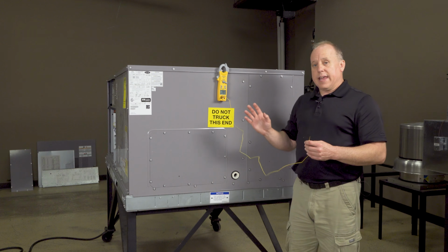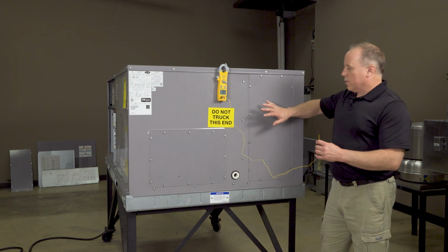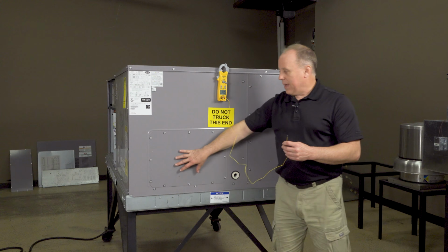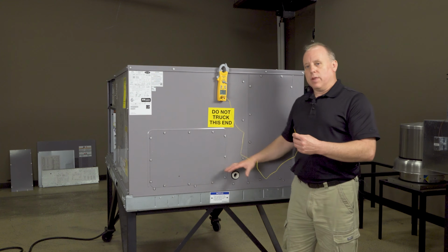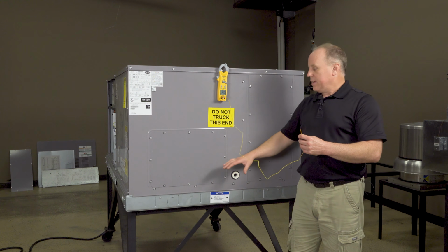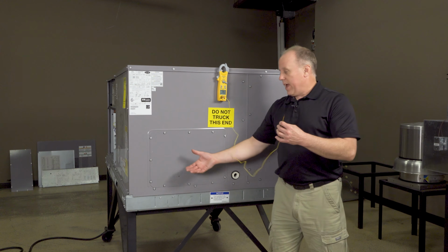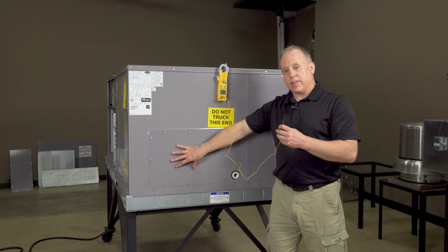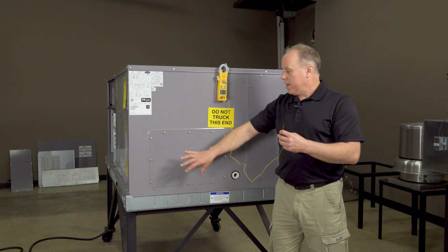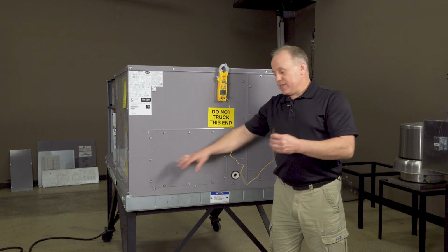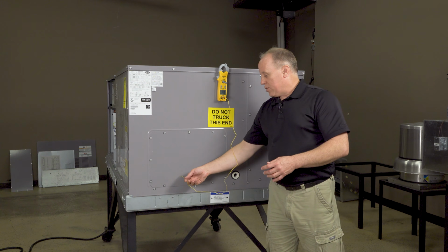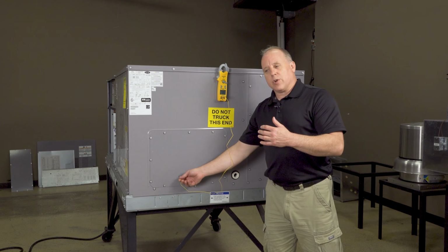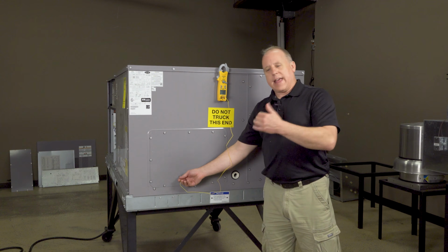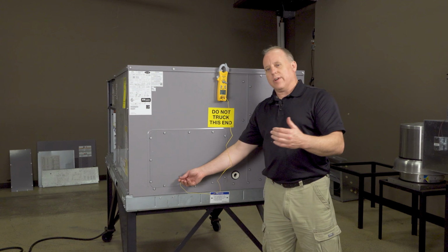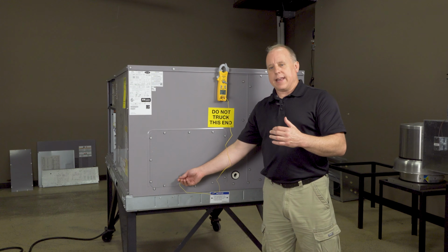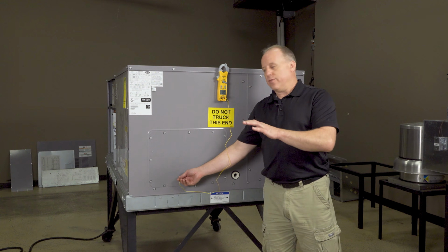Now, if we were running in the heat mode, we'd do the exact same thing. Return temperature, supply temperature. Again, we could do it just below the unit in ductwork, if that's the case, or even a side discharge. If we had this ductwork attached to the side of the unit, we'd be able to access there also. But when we get in on the heat side, again, we get just inside. Be careful, make sure when you put that in, you're not hitting anything metal, because that would be the heat exchanger, and that temperature is going to be extremely hot. So you just want to be in the airflow.